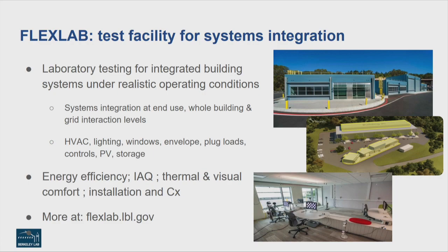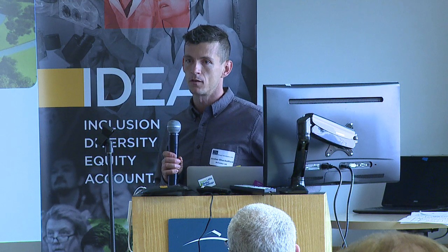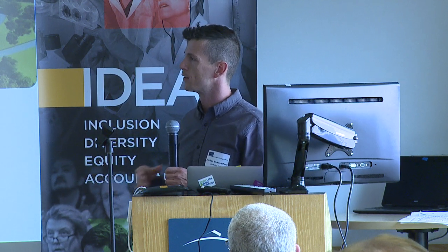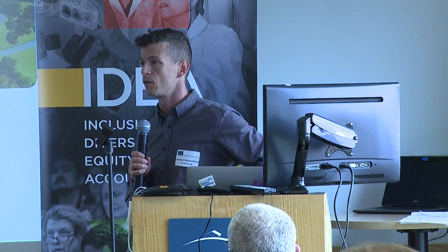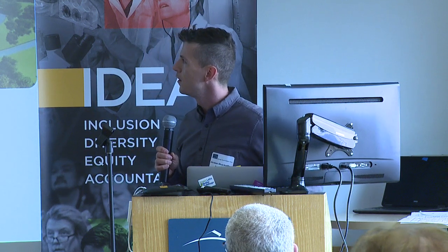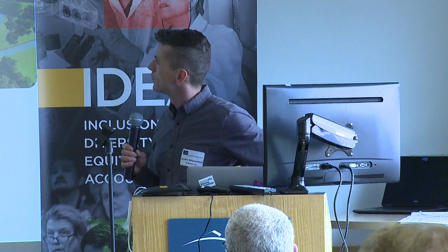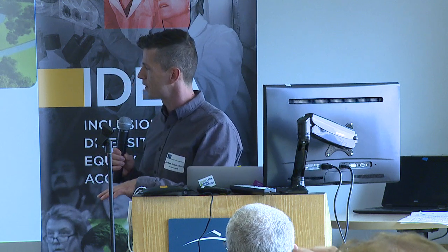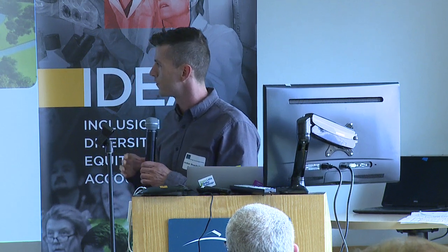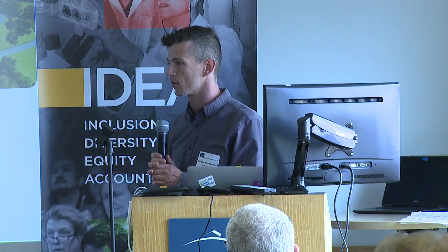Everything in FlexLab is measured—in the slab, walls, and ceiling we have thermistors. We've got luminance sensors everywhere, daylight glare probability packages that measure glare from windows, and on the hydronic side, chilled water and hot water temperature changes so we can characterize HVAC loads. All the facilities are side-by-side test cells of the exact same dimensions, so we can run a base case and a test case in parallel, in real time, and see how energy usage, air quality, or other comfort parameters vary between the base case and the retrofit.